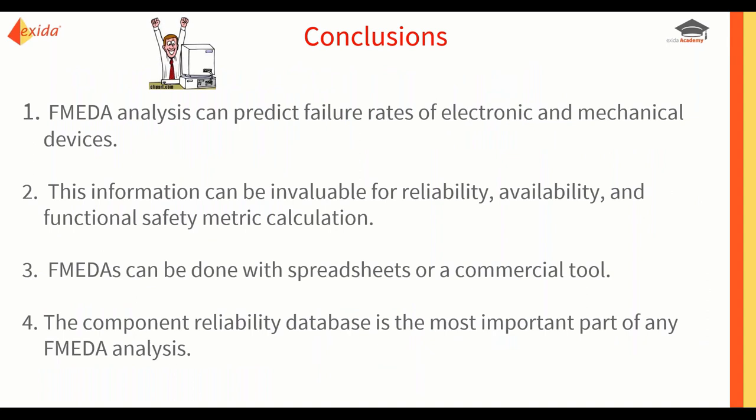So in conclusion, the FMEDA analysis, obviously it can predict failure rates of electronic and mechanical devices. This information can be invaluable for reliability, availability, and functional safety metric calculation. FMEDAs can be done with spreadsheets or a commercial tool. And the component reliability database, as I say, is the most important part of any FMEDA analysis. But I think one other key takeaway from this webinar today is the time when to do an FMEDA, and it's when your design has been somewhat settled but before any physical product or prototype is being made.